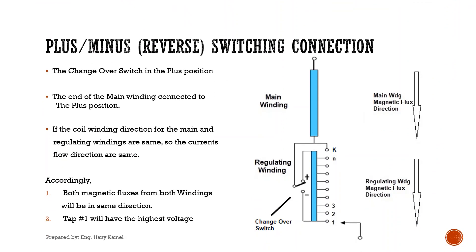For plus-minus, or reverse switching connection: if the changeover switch is in the plus position, the end of the main winding is connected to the plus position. If the coil winding direction for the main and regulating windings are the same, the current flow directions are the same. Accordingly, both magnetic fluxes from both windings will be in the same direction. In this case, tap number 1 will have the highest voltage.